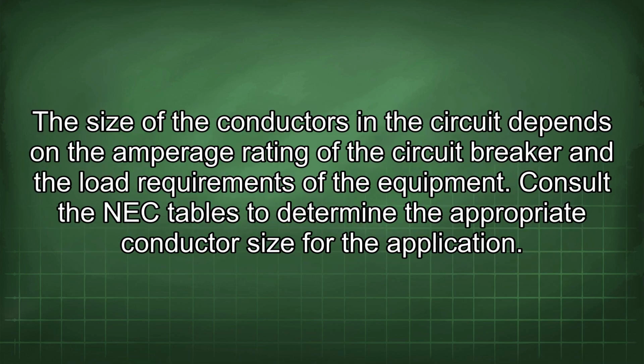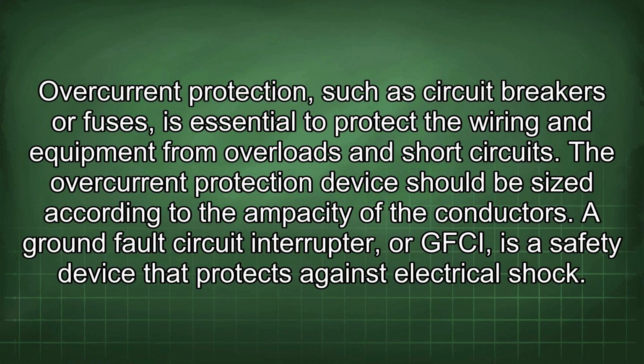The size of the conductors in the circuit depends on the amperage rating of the circuit breaker and the load requirements of the equipment. Consult the NEC tables to determine the appropriate conductor size for the application. Overcurrent protection, such as circuit breakers or fuses, is essential to protect the wiring and equipment from overloads and short circuits. The overcurrent protection device should be sized according to the ampacity of the conductors.